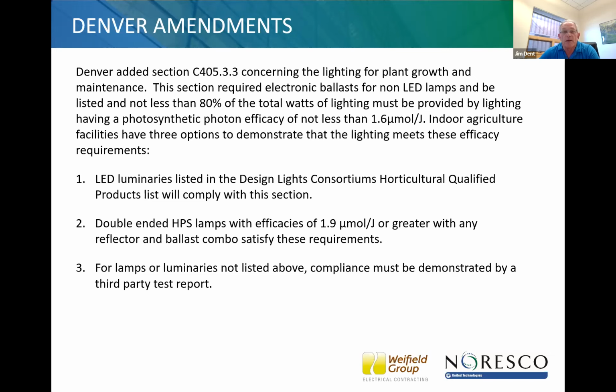Denver added section C405.3.3 concerning lighting for plant growth and maintenance. Both Denver and Boulder have this amendment. You'll see this again in the Boulder slides. And for plants, lumens, or how much candle power, how bright it is, isn't really what they want to measure. They want to measure the photosynthetic photon efficacy. So how many photons per second. So Denver and Boulder have both adopted a photon efficacy of not less than 1.6 micromoles per joule. Denver listed 3 ways to achieve that. Boulder did not list the 3 ways to achieve that, and Fort Collins did not address this in their amendments to the code. Next slide, Kevin.